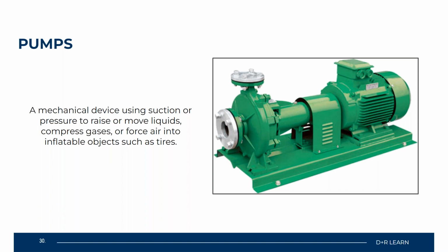Next, we have our pumps, and our pumping system is pretty much what we have here on screen. A system that is going to move liquids or any type of gas where it's needed. Pumping systems can be found in most of your hydronic applications for facilities, and they assist in applications such as supply and return of boiler water systems, supply and return of chiller water systems, your domestic heating water supply, your sump pumping stations, and also supply for gas or any type of oil if it's being utilized. So once again, pumps are just mechanical systems used for moving liquid or any type of gases to the applications or components required.